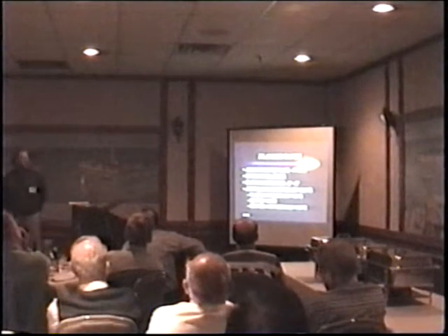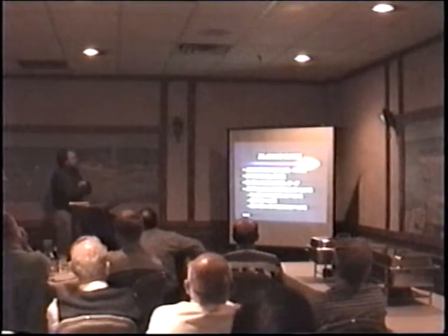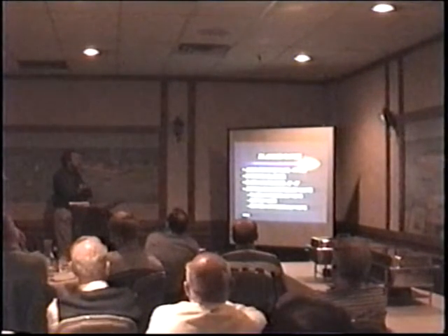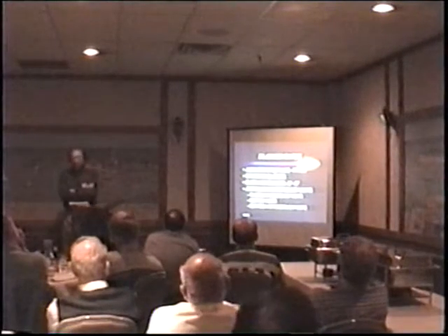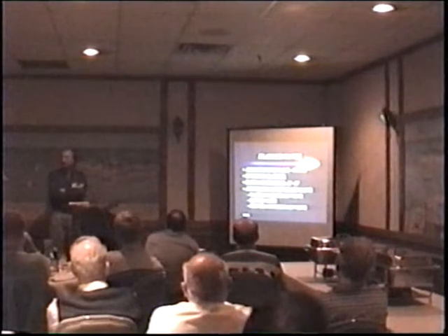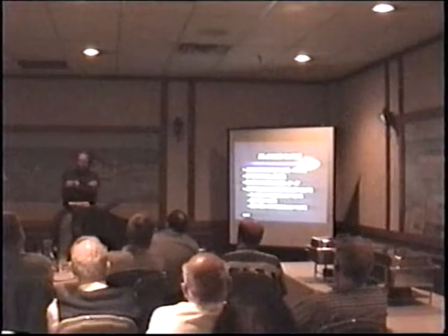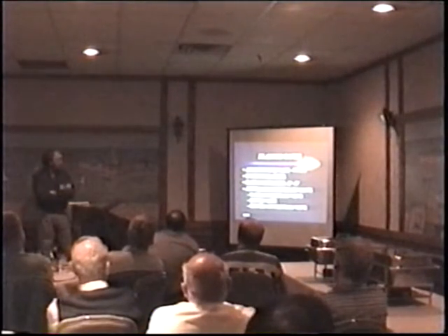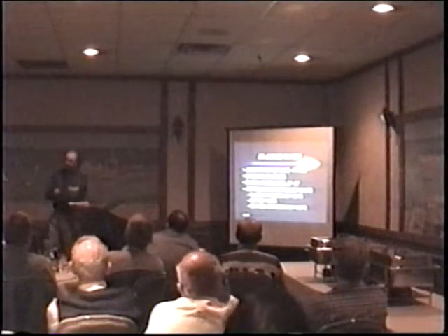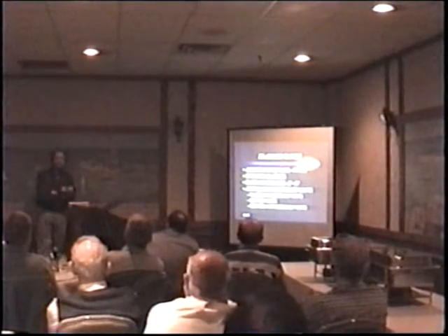Again, I'm a little biased. I like bladder tanks, so we're going to talk a little more about bladder tanks. Pressure tank, of course, the system is UL/FM like any of the commercial systems are. The tank is 175 psi. You've got an internal bladder that's flexible. Concentrate goes inside the bladder, and then the water comes in, surrounds the bladder, and squeezes it down uniformly until it's discharged. Various ratio controllers, 2 inch to 8 inch in size, fit into the sprinkler riser. They handle flows as low as 30 GPM and as high as 5,000 GPM.